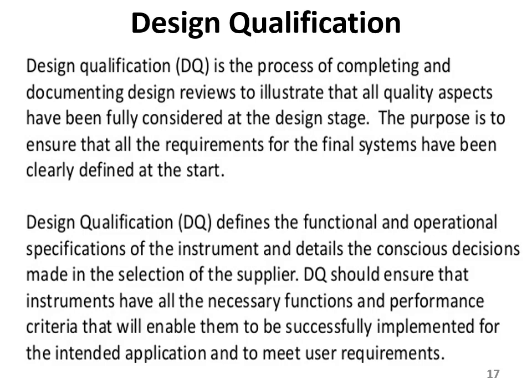the functional and operational specifications of the instrument and details regarding the conscious decisions made in the selection of the supplier. DQ should ensure that the instrument has all the necessary functions and the criteria that are going to enable you and the machine to successfully go through the system and implement all the requirements and the needs of the user.